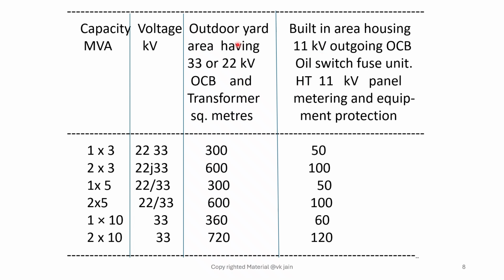This table describes the requirement of outdoor yard of a particular 33 or 22 kV substation and the built-in area housing 11 kV outgoing, oil circuit breaker, oil switch fuse unit, etc. So this table has been prepared by CPWD depending upon the capacity of the system in MVA and preferred voltage. This provides the outside area of the substation and this provides the inside area of the substation.